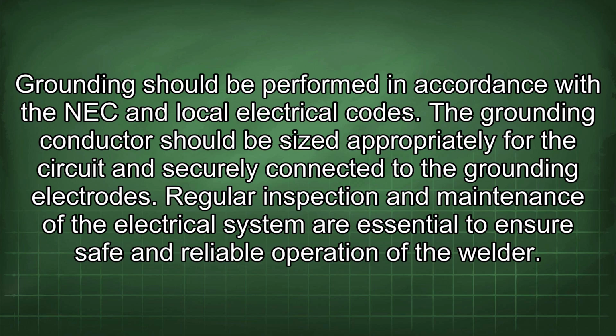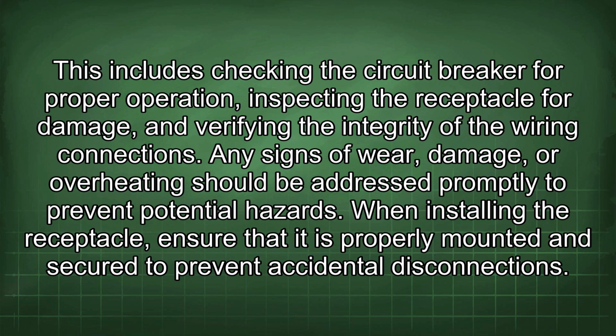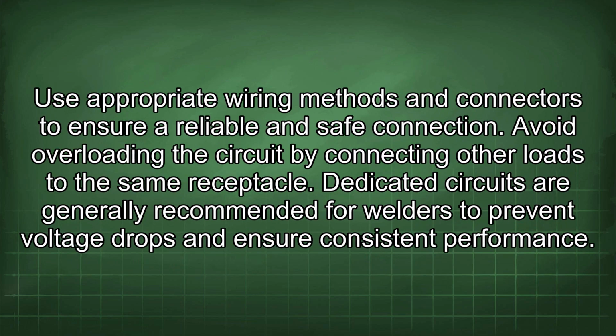Grounding should be performed in accordance with the NEC and local electrical codes. The grounding conductor should be sized appropriately for the circuit and securely connected to the grounding electrodes. Regular inspection and maintenance of the electrical system are essential to ensure safe and reliable operation of the welder. This includes checking the circuit breaker for proper operation, inspecting the receptacle for damage, and verifying the integrity of the wiring connection. Any signs of wear, damage, or overheating should be addressed promptly to prevent potential hazards. When installing the receptacle, ensure that it is properly mounted and secured to prevent accidental disconnections. Use appropriate wiring methods and connectors to ensure a reliable and safe connection. Avoid overloading the circuit by connecting other loads to the same receptacle. Dedicated circuits are generally recommended for welders to prevent voltage drops and ensure consistent performance.